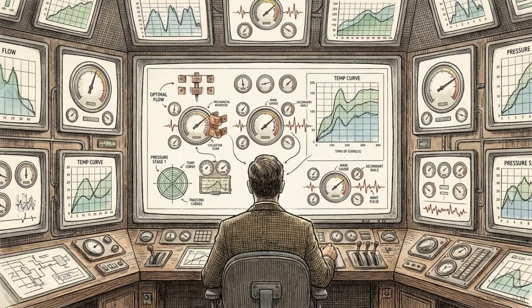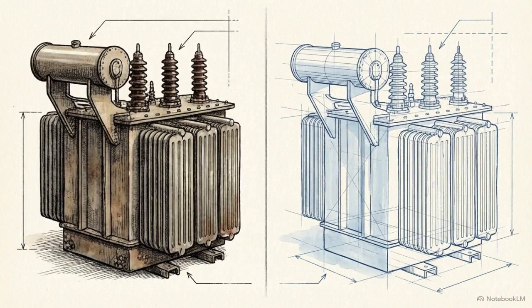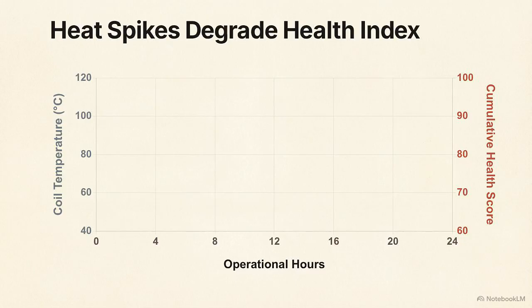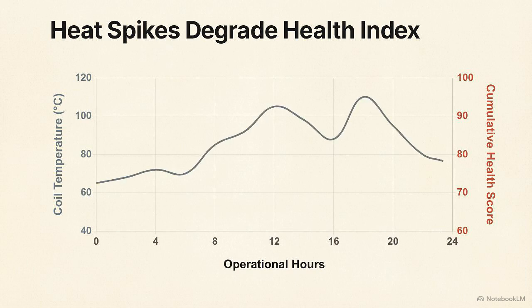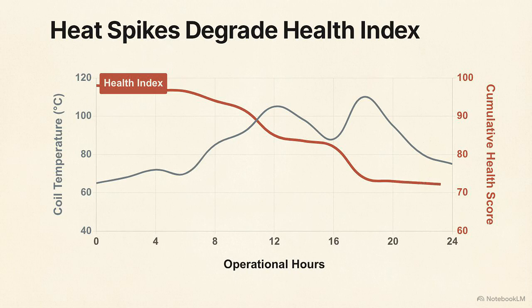The entire investment in sensors, gateways, and cryptography exists solely to populate this screen. The interface acts as a digital twin of the physical transformer. It aggregates disparate variables, voltage anomalies, harmonic distortion, and the internal coil temperatures into a single continuous feed. The system processes these variables to generate a health index. A health index is a single numerical value calculated from real-time operational data, telling the facility manager exactly how much operational life the transformer has left based on its cumulative stress.